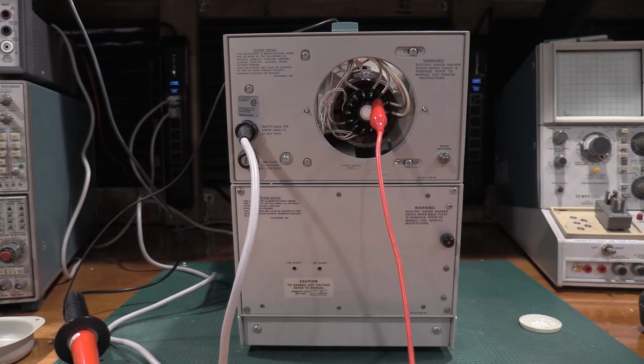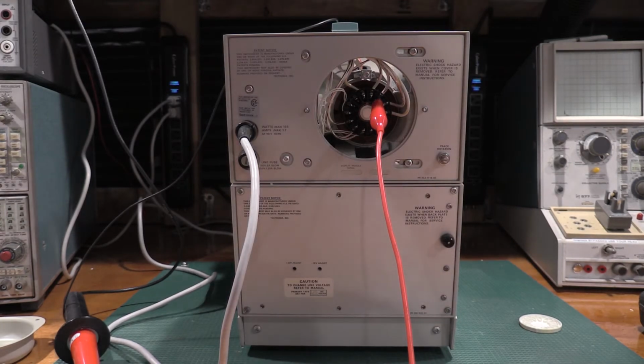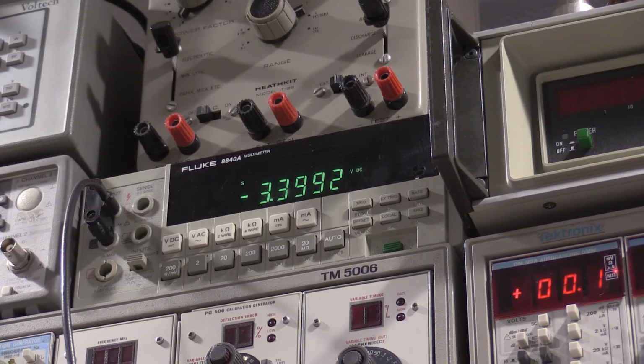And I am supposed to have approximately 3,400 volts. Anything from 3230 to 3570 is fine. My meter is telling me we are at 3,433. So that is well in spec. But since we're doing a complete calibration, we can adjust it. Now, when doing these adjustments, use extreme caution. You do have negative 3,000 volts exposed on the bench. Well, when we're dealing with 4 kV, plus minus 2 volts is good enough for our lab.